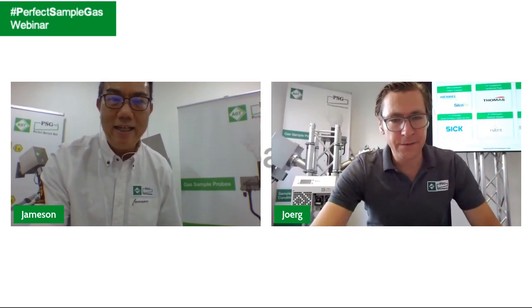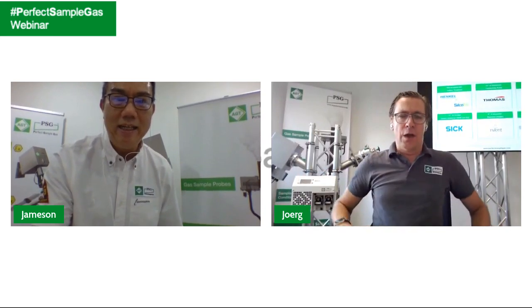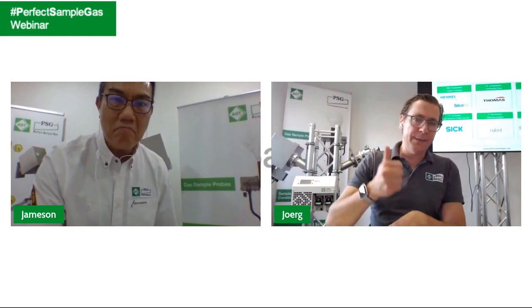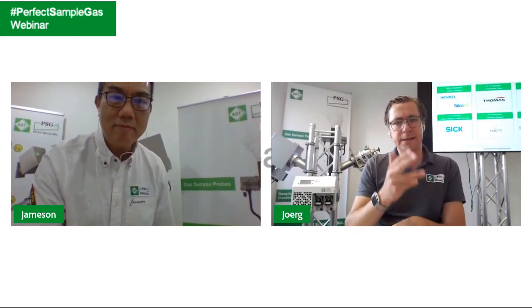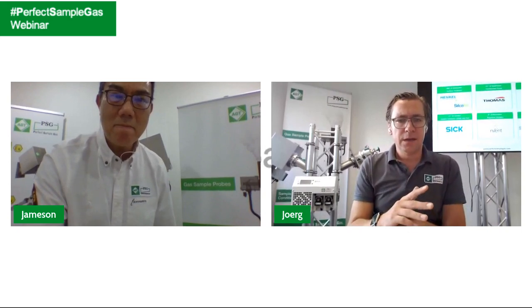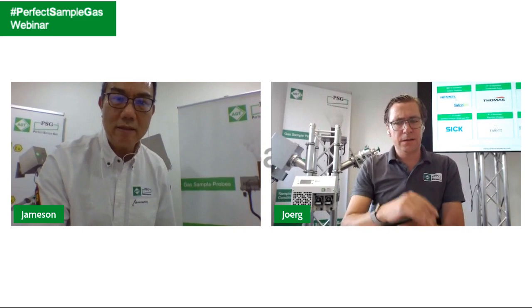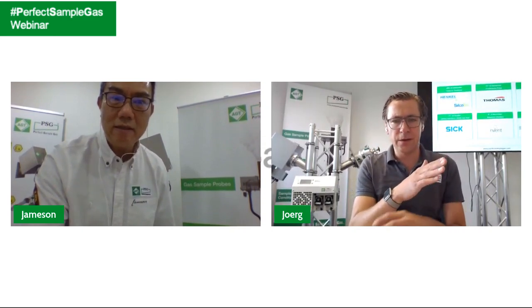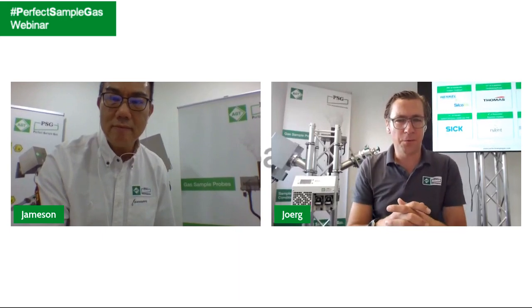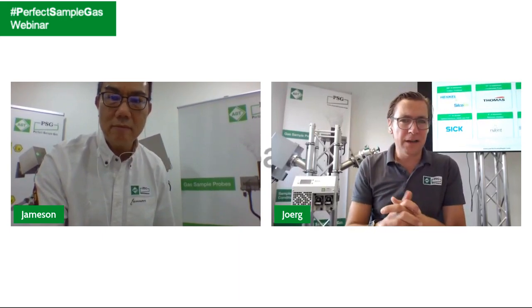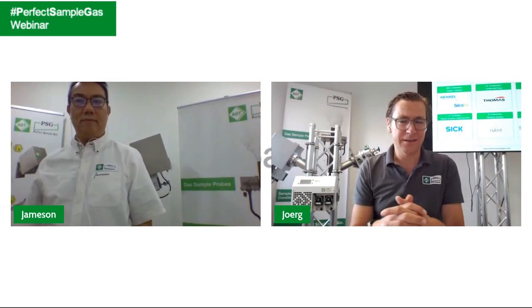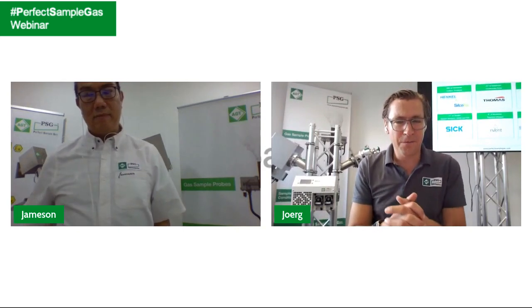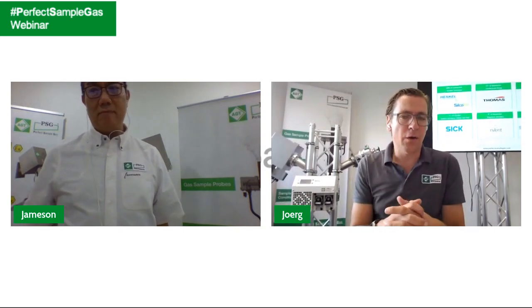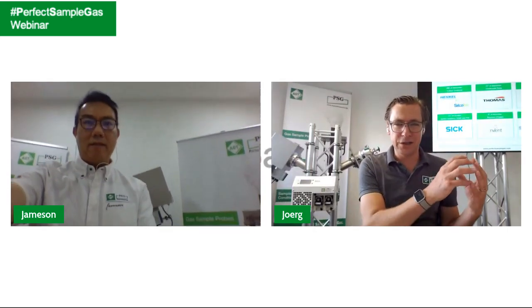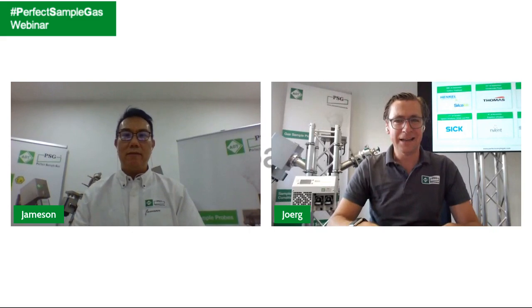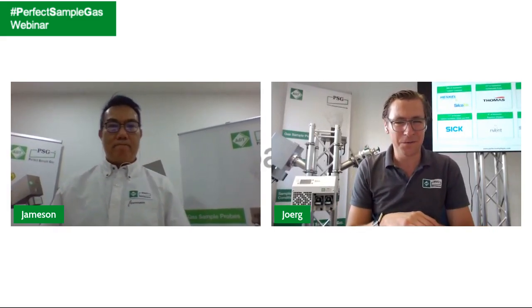But I think we really have to look at the time. Primary probe sampling, filtration, filter surface, back purging. That's what we covered. Like we said, if you manage to remove particles, and you're not running into condensation, so the probe has to be perfectly heated, there's already a good chance that from the initial sampling to the transportation of the line, nothing should go wrong. Is this something you would confirm, Jameson?